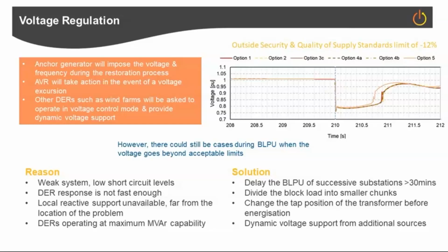There'll only be a certain length of feeder line or length of network that you can actually withstand at a generator DER level. So again, there seems to be a need here for increasing the short circuit levels, reducing the impact on voltage deviations with the input of additional DER support. So that's a big conclusion that we've come to.